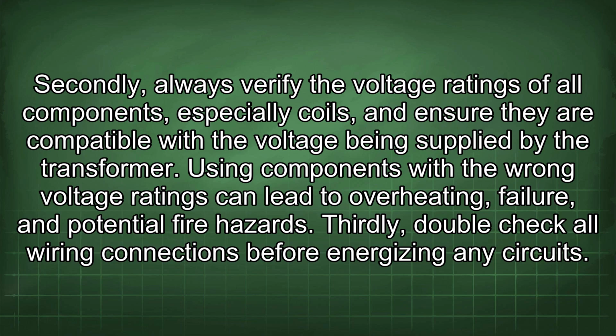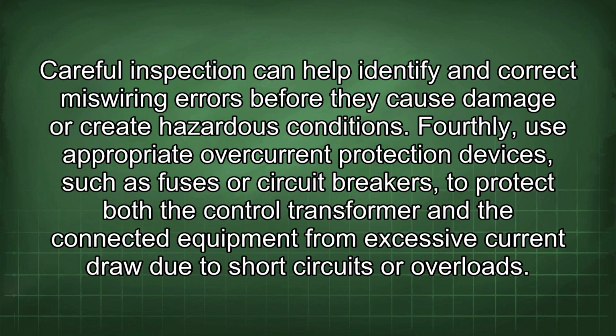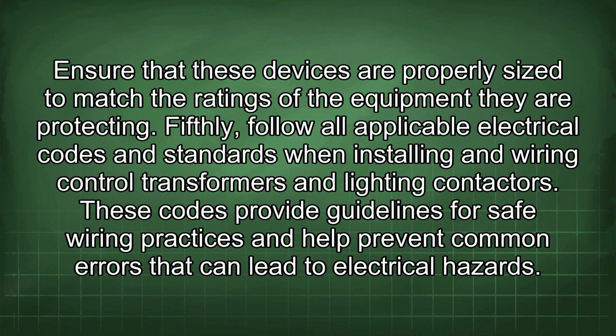Thirdly, double-check all wiring connections before energizing any circuits. Careful inspection can help identify and correct miswiring errors before they cause damage or create hazardous conditions. Fourthly, use appropriate overcurrent protection devices, such as fuses or circuit breakers, to protect both the control transformer and the connected equipment from excessive current due to short circuits or overloads. Ensure that these devices are properly sized to match the ratings of the equipment they are protecting.